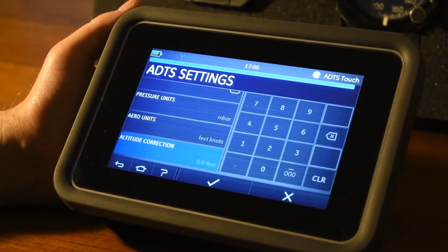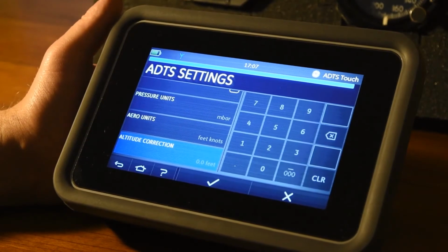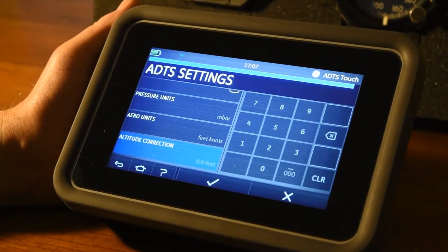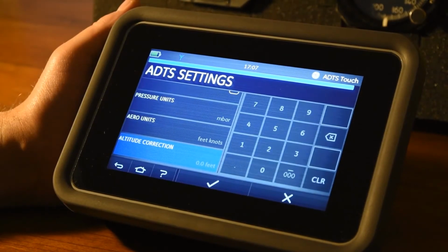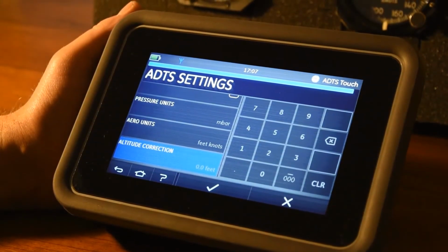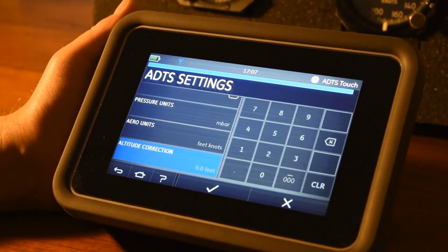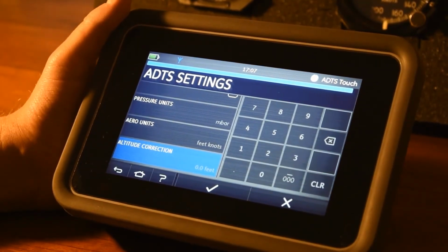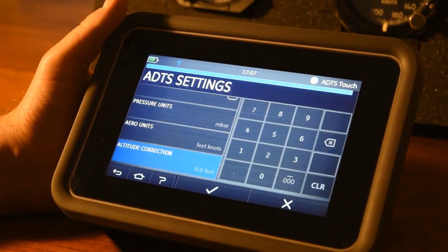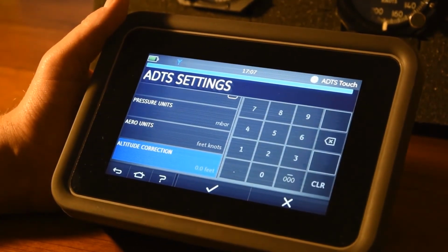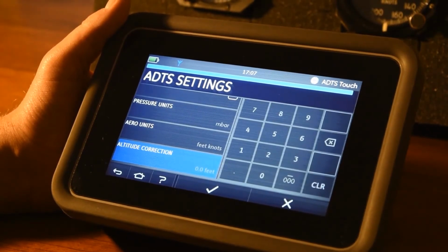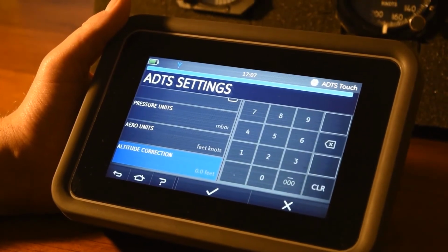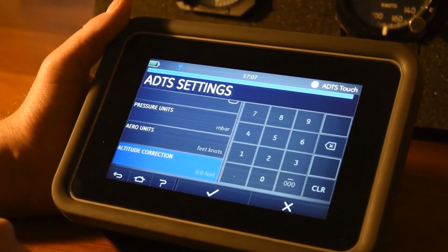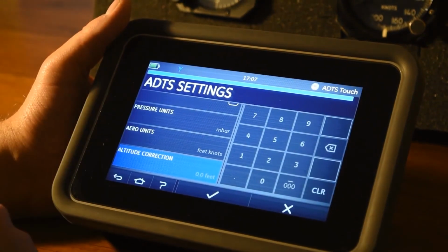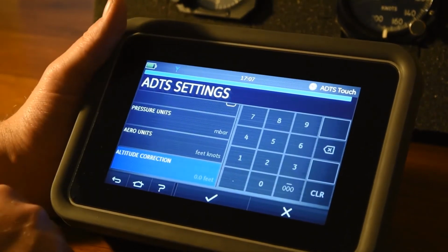So I think it's 22 feet at 40,000 feet error, which is outside of the limits of where it should be. For example, if we were looking at something like a Boeing 747, the height of the cockpit where the instruments are relative to the ADTS is quite a difference. If you don't put a correction factor in there, then you're adding the height of the aircraft's instruments relative to the air data test set into your overall error. That's simply entered in feet, or whatever units you're working in—if you're in meters, it'd be in meters. So you simply go in, enter the password and enter the height.